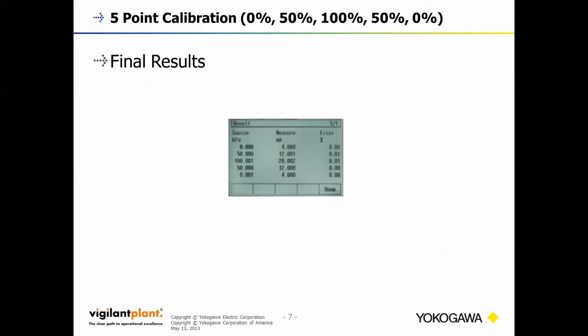So after doing the 5-point calibration, here's our final report from the CA700 screen. You can see our error is really good, and that's pretty typical of our Yokogawa pressure transmitter. So really, this is just a verification. This calibration, that's all you're doing is verifying that the error is within tolerance. So in this case, you wouldn't have to do anything. You wouldn't have to trim the transmitter or do anything. It's in perfect working order, and you can kind of expect that out of a Yokogawa transmitter.